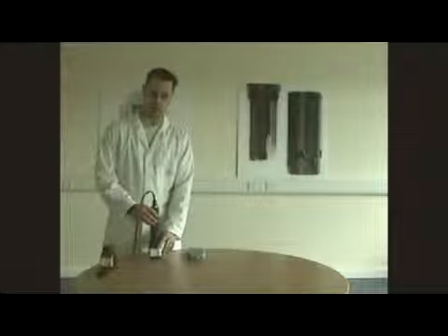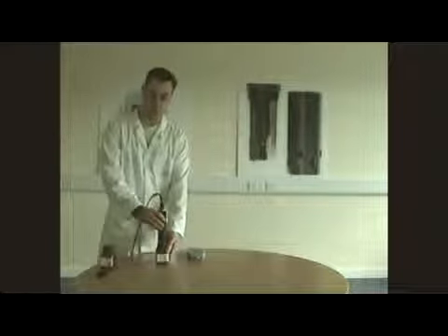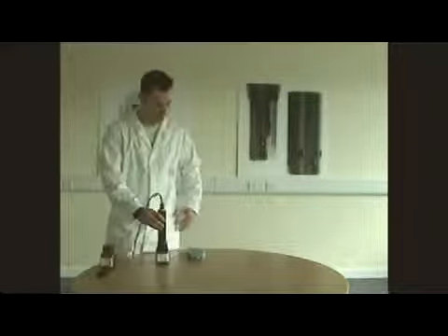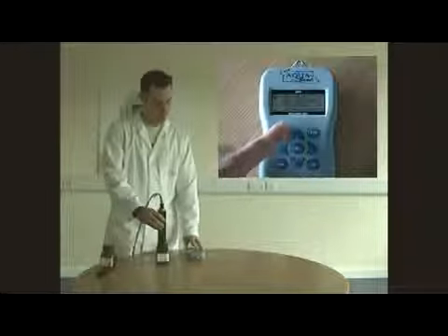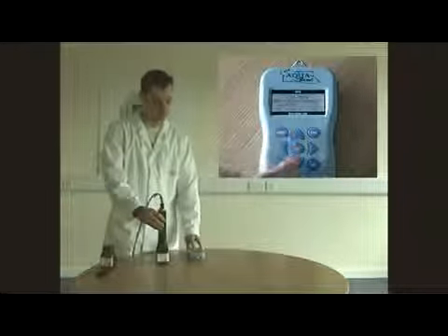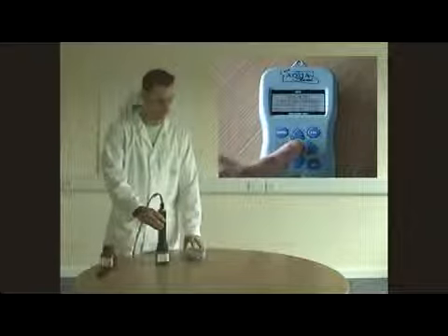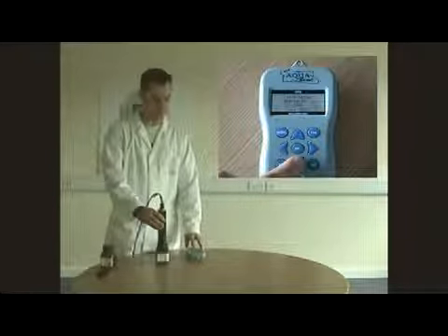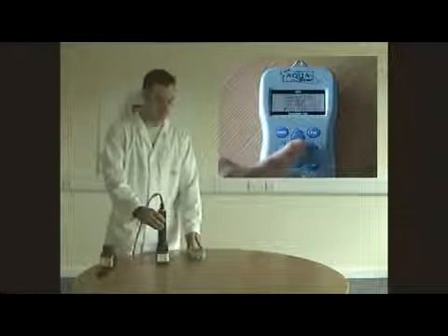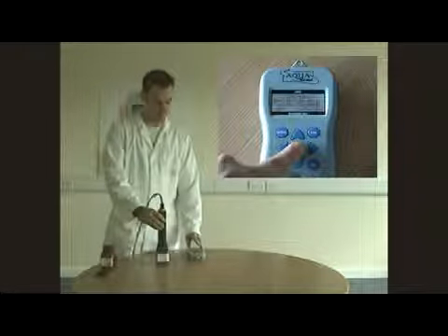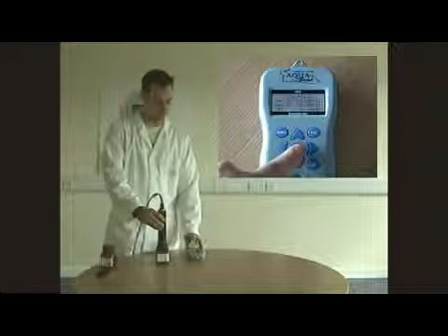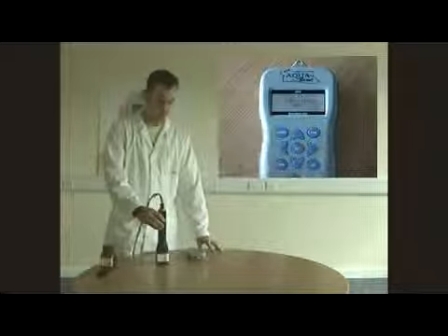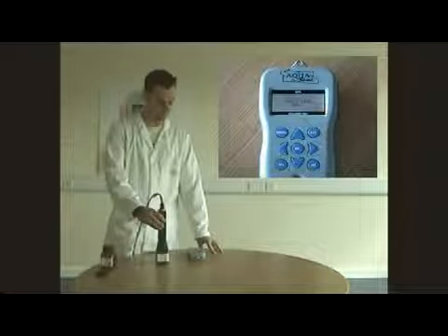We're now going to carry out calibration at pH 4.01. This will give us our 2-point calibration. We select from the menu, go down to calibration. This time we select full cal, and within this menu we select pH ORP. We're given a group of options here. I'm going to scroll down to pH 4.01 and press OK. This will begin the stabilisation.